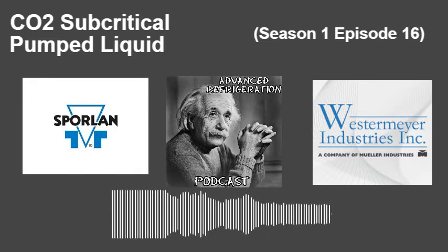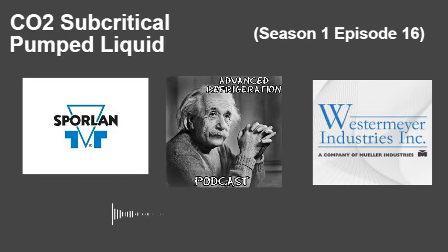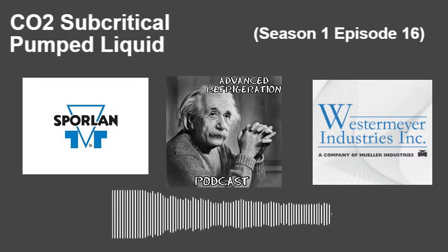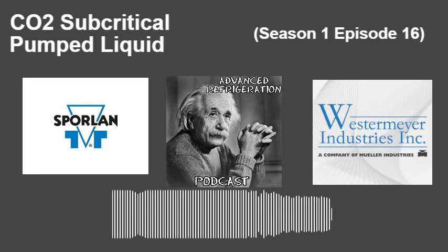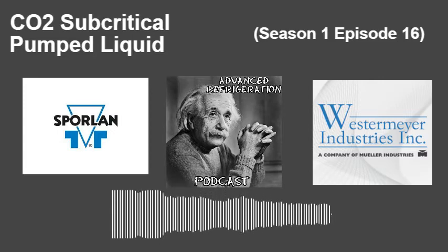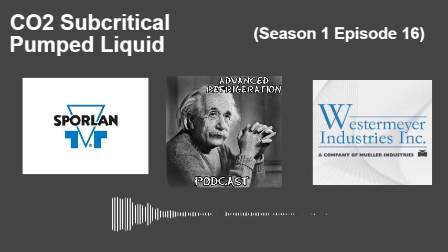Now, we did like 12 of these stores up here, and the guys were pretty good after store number 2, where we learned if you put the valves in backwards, you can't shut them off. And then you've got a real problem. And there are still stores out there where the installers didn't pay attention to where the check valves are going, and now you've got to blow off an entire line set. So an entire loop, which becomes a problem because it takes forever.